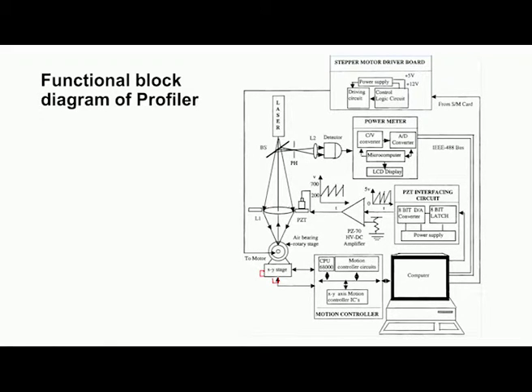And now we can see here we have the objective lens which is fixed to the PZT. For focusing the light onto the surface we use the PZT, and using the PZT the lens can be moved up and down for focusing purposes, and this PZT movement is connected to the computer via this PZT interfacing circuitry. And then we have the gas laser source, the beam splitter, and then another lens. The light will pass through this pinhole. Reflected light will pass through the pinhole and is made to fall on the detector via the lens L2, and then the light intensity is measured in terms of microwatts. So, there is a power meter to measure the wattage of the light intensity.